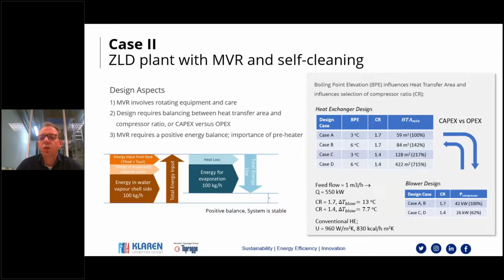Looking at the top side, for example, cases A and B, both with a compression ratio of 1.7. If the boiling point elevation increases from 3 to 6, my heat exchanger area goes from 100% to 142%. So a substantial impact.